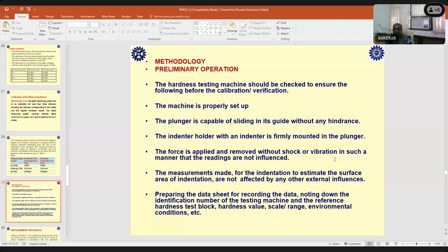So we have to make sure there isn't any other disturbance. Whenever you are using hardness measurement equipment, you shouldn't be running any other motor or anything like that in the nearby area. Suppose a compressor is running in the next room and suddenly switches on, it can cause some vibration. If there is vibration while you are making an indentation, then definitely the applied force will vary, and that will also affect your indentation geometry, and that will affect your measurement. So you have to make sure there is no other machine, particularly a compressor and things like that. If it is running nearby, you have to isolate your hardness machine.